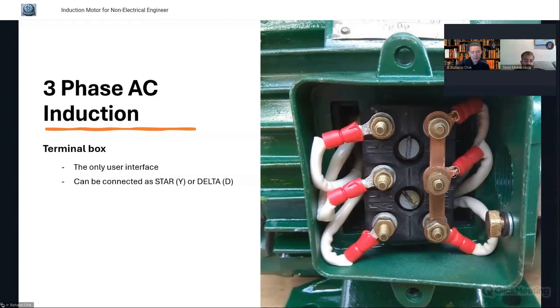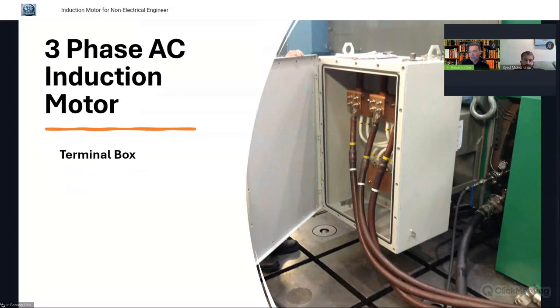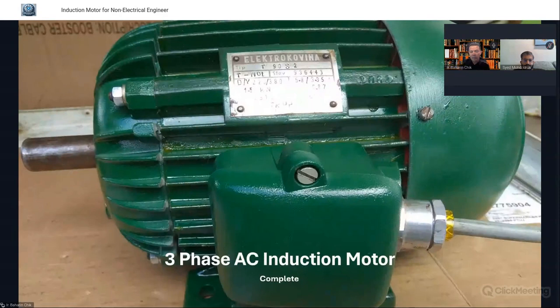So this is the interface that we have with AC induction motors, the terminal box. So this is where we connect, where we short the terminals for the Y connected motors. This one will go to the supply side. Now for Delta, we have seen that it is connected directly instead of shorting this terminal. This is another terminal box for an HV motor. And then when you assemble all these LV motors, this is how it looks.